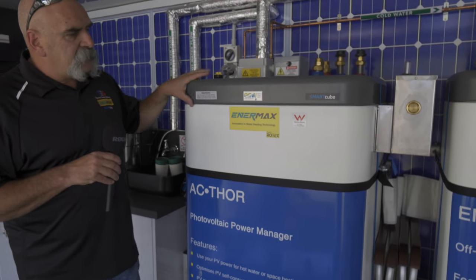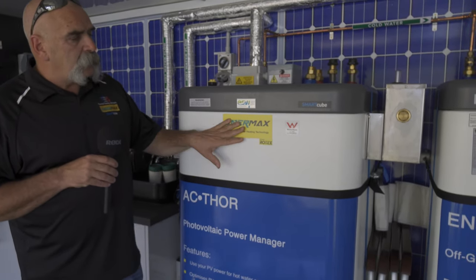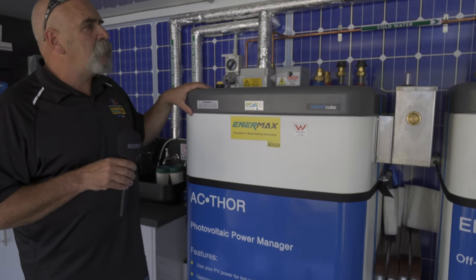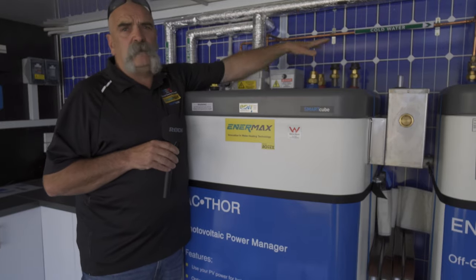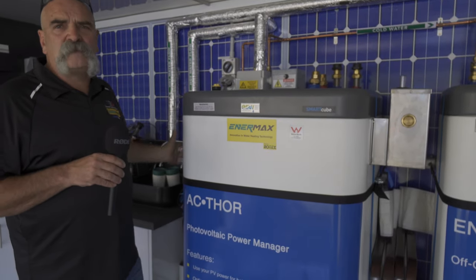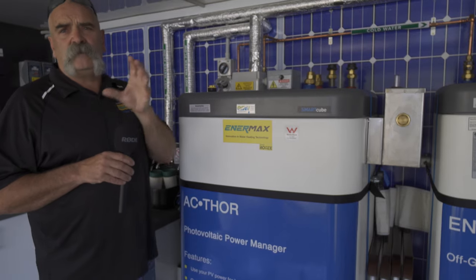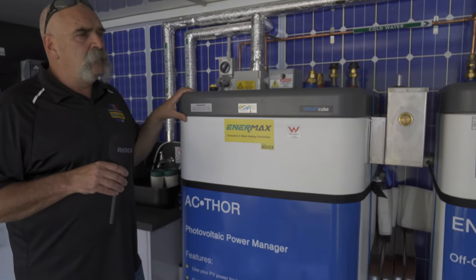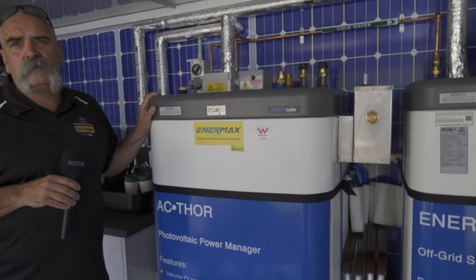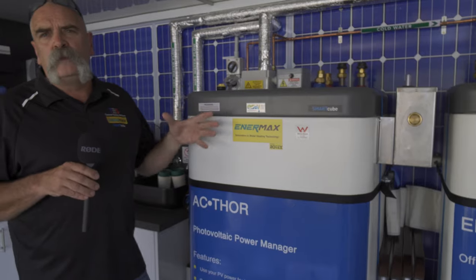The Enermax tank has been in the country for almost 30 years — traditionally called a Rotex tank, but now rebranded as Energy Smart Water's own brand Enermax. It's a 500 litre tank that can have multiple coils, so we can do hot water, hydronic heat, a spa, and a pool off one tank depending on the heat source. The tank can be heated with the AC Thor, a heat pump, or any waste and reclaim energy. It's a thermal battery — like a heat bank where we can bring multiple energy sources in and take multiple heat outputs out.